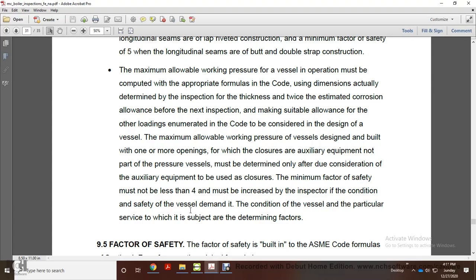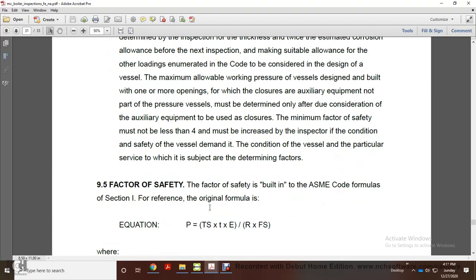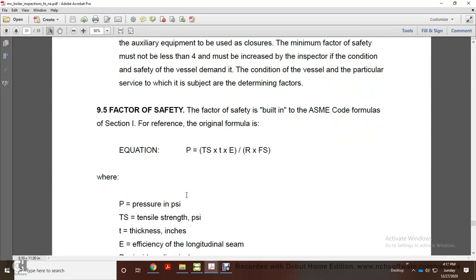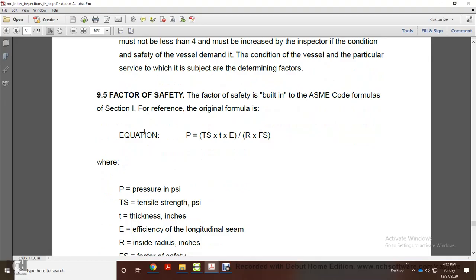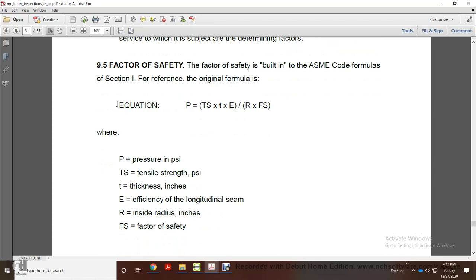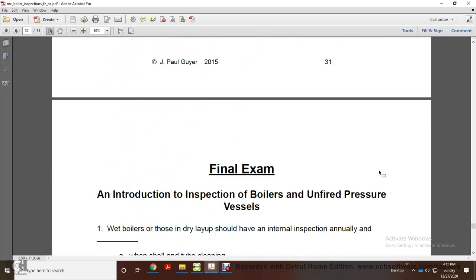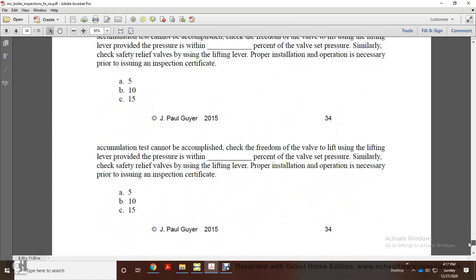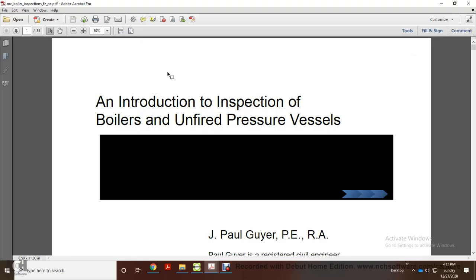The condition of the vessel and the particular service to which it is subjected are determining factors in the factor of safety, which is built into the ASME code formula in Section 1 for reference to the original formula. The equation is P equals TS times t times E divided by R divided by FS. P is pressure in psi, equal to tensile strength times thickness in inches times efficiency of longitudinal seams, divided by inside radius in inches times the factor of safety. And then it goes into the exam. And that was the introduction to inspection of boilers and unfired pressure vessels.